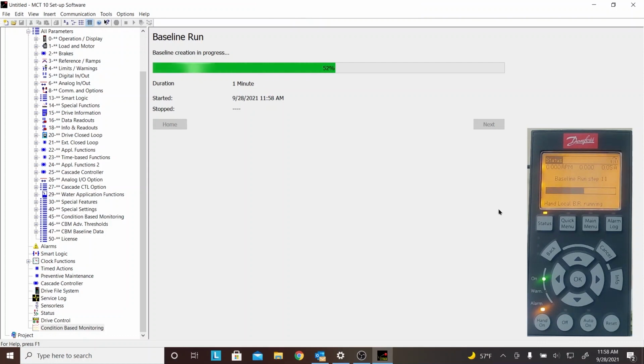So at this point, we're really looking at the LCP 102, the graphic keypad that comes standard with every drive. It's not an extra option. And this thing will data log. It will graph like a scope. It has easy to push buttons for alarm, HOAs, it has indicating lights on the side, even has a condensed programming manual in the info button over in the far right in the mid center here. And the OK button does the selection and storing. Very simple keypad. By the way, this is an IP65 keypad as standard. So even if you mount this on the door of an enclosure, you have the IP65 integrity.